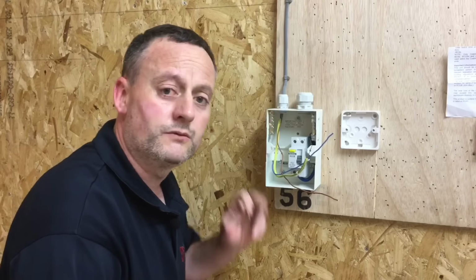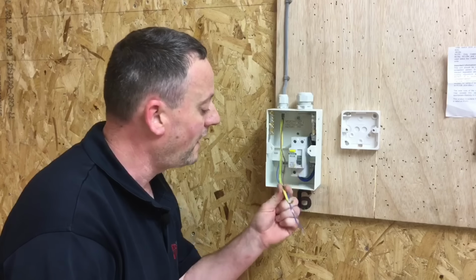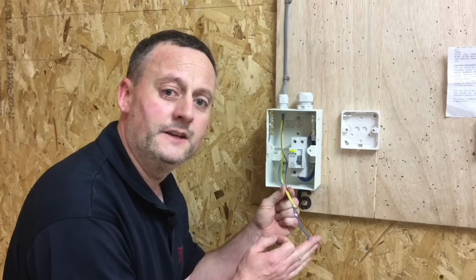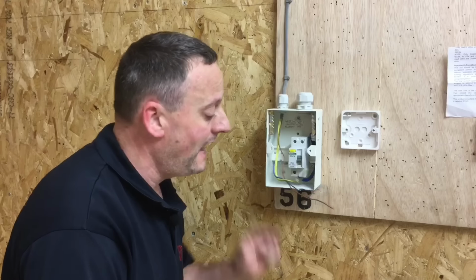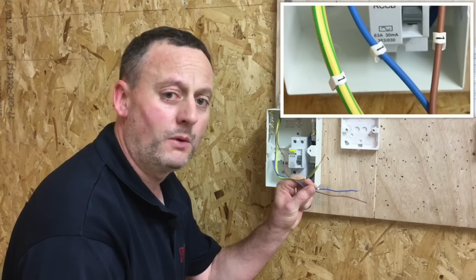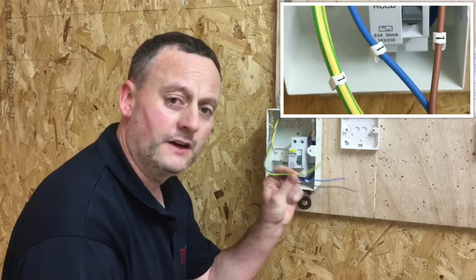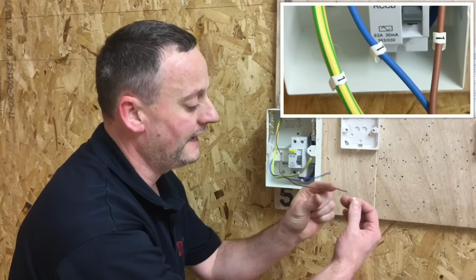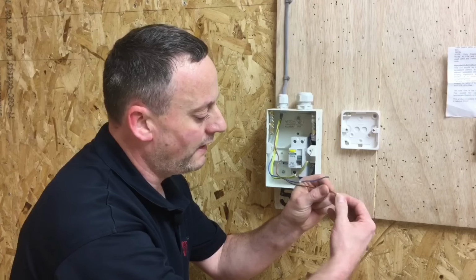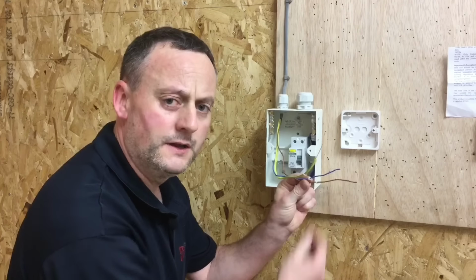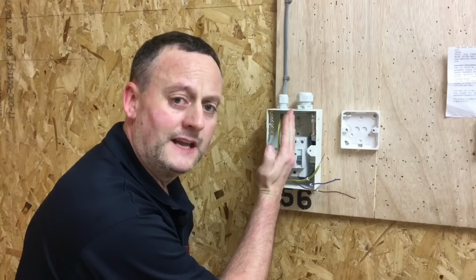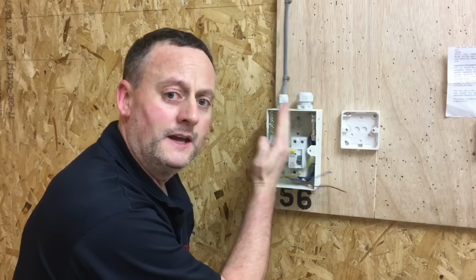So my conductors are ready for termination. The conductors are longer than the consumer unit again, so we've got plenty of cable to work with there. And I've identified at the moment my neutral with a number 1 and my circuit protective conductor with a number 1. And now I'm going to take an identifying tag and roll it over the line conductor to also identify it as number 1. Circuit breaker position next to the main RCCB is circuit number 1.